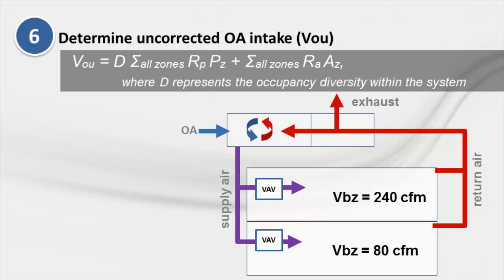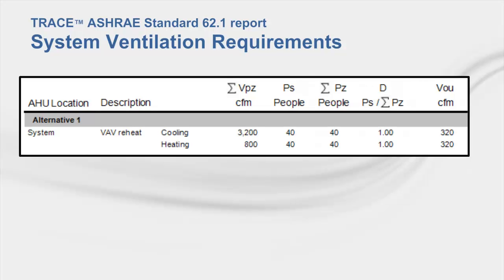In equation 6-6, the variable D represents occupant diversity, which can be entered into TRACE in the Advanced window within Create Systems in the population diversity input. Assuming occupant diversity equal to 1, V sub OU equals the sum of the breathing zone air flow rates, which is 320 CFM. The TRACE report shows the uncorrected outdoor air intake flow, V sub OU, for the system in the System Ventilation Requirements section.